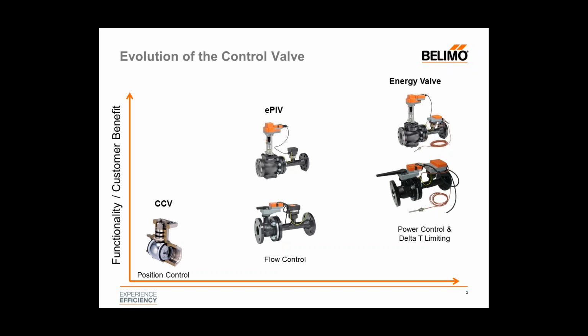With a pressure-dependent valve, typically the DDC signal responds to a specific valve position. Then when you start moving towards pressure-independent valves, that control signal now directly correlates to a specific GPM. We've taken that even one step further with the energy valve, where now we have some further advances with control technology. One of the things that we have is what's called power control. So not only does it respond to pressure independence by maintaining pressure-independent flows as pressure either increases or decreases within a system, flow across the ball is going to remain constant at its set GPM.